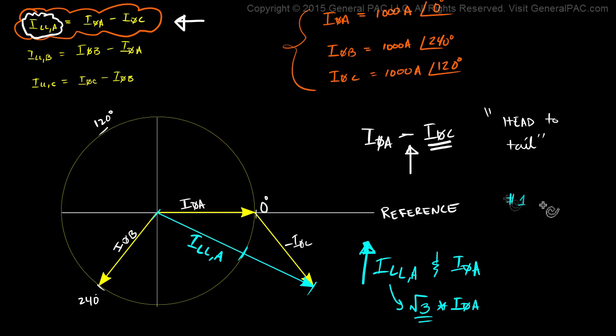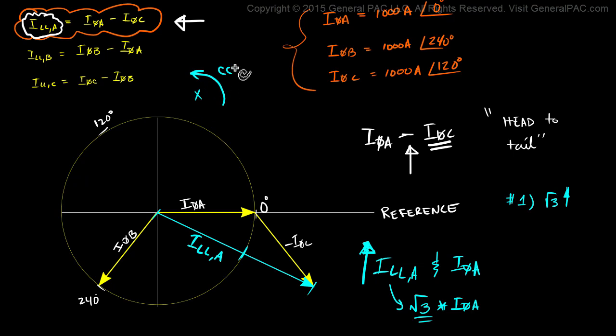So that's the first observation: our line current is the square root of 3 times larger than our phase current. Also notice that our line current has a phase shift associated with it. If all the phasors were rotating in a counter-clockwise direction, which is what they should according to international standards, we will see that the line current has a 30 degrees phase shift. So number 2: line current has a 30 degrees phase shift with respect to phase current.